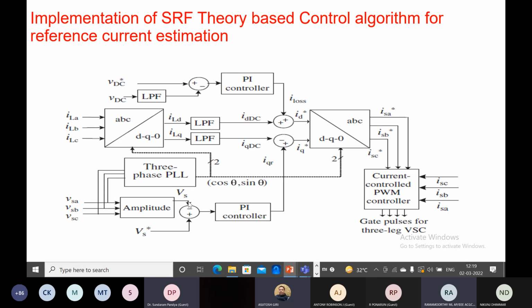The reason is we are taking another error controller for amplitude calculation and amplitude reference. At the same time, we are maintaining the frequency, or the DC link constant, and we are maintaining the voltage at the PCC constant. The supply line voltage should not go down, meaning there should not be any sag or swell over the supply system.